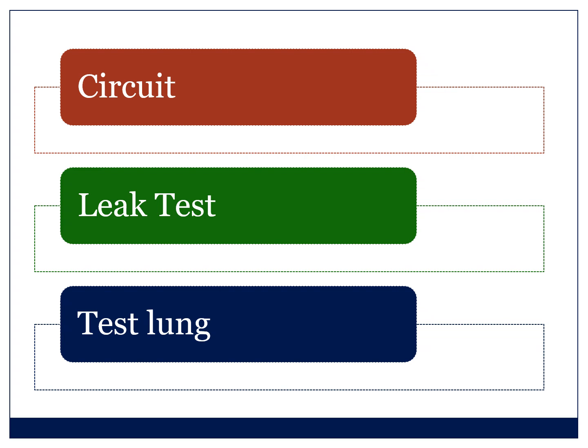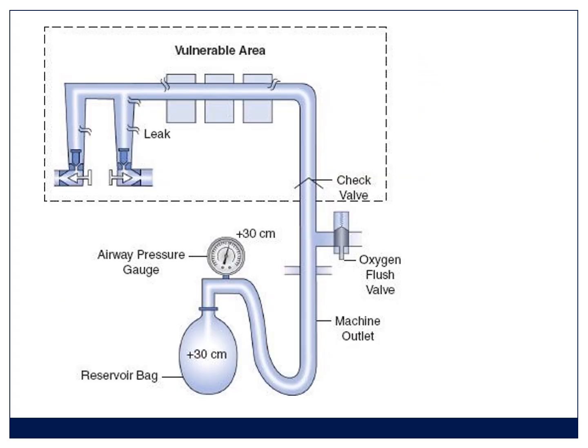Now, an acceptable leak is actually less than 200 mils. When we used the old Boyle's machines in the old days, we would accept up to 2 liters. So we accept much less leak now as an acceptable leak. The commonest sites of leak are the circuit, the carbon dioxide absorber, the vaporizers, and the bellows, and you need to go and find these leaks if there's a leak. I'll just run through that quickly.